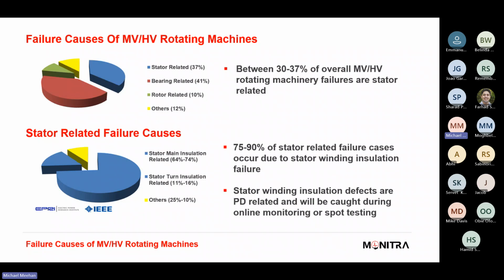Stator winding insulation defects are PD related and will be caught during online monitoring spot testing. 75 to 90% of the stator related failure causes occur due to stator winding insulation failure. So when we're looking at insulation failure, typically it is PD. You can detect that through PD testing. It's probably the most effective tool, and the reason it is the most effective tool is because you can do it while the machine's running. You're not having to wait for an outage event to do some offline testing. There are great advantages with tan delta and all the other testing, so it's definitely got its place and is definitely a requirement to keep your machine healthy.